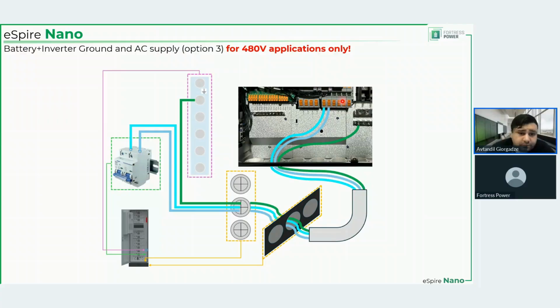So if backup ports or smart ports, doesn't matter, are unoccupied by something else, let's say you have a smart port right here, right? And that smart port doesn't have AC PV, doesn't have a generator, doesn't have smart load, you can use it as the load output to the auxiliary AC supply and connect the ground to the ground bar and connect that single phase to the breaker that we were talking about before, the AC supply breaker on the right side of the inverter. Again, this is only for 480 volt applications. So this is totally fine.